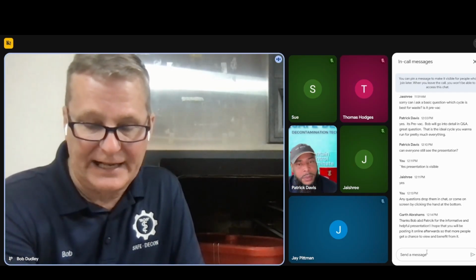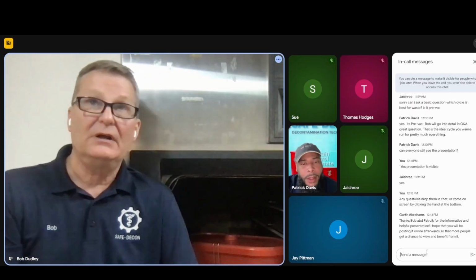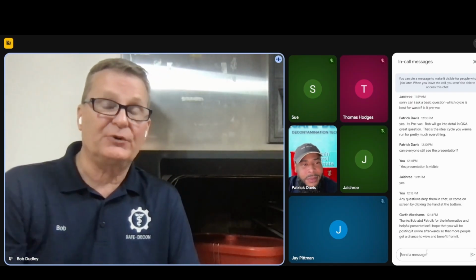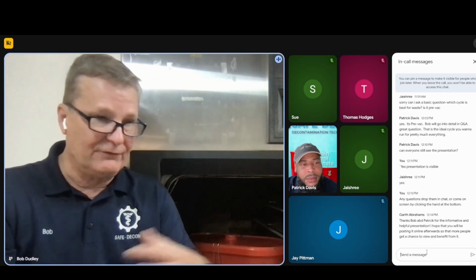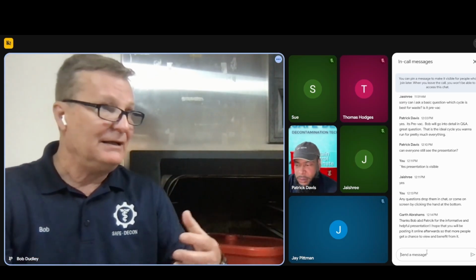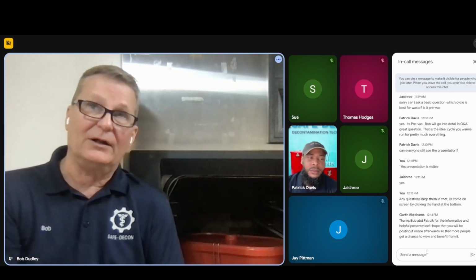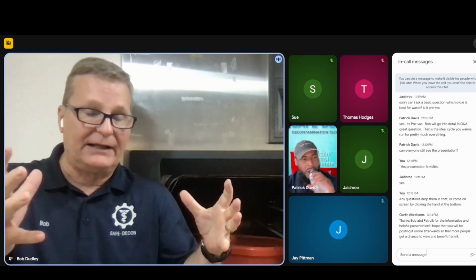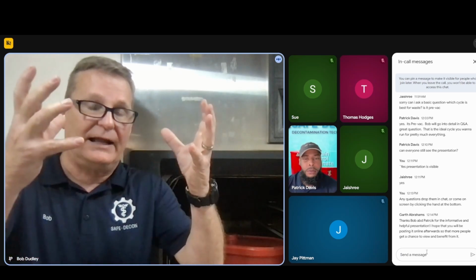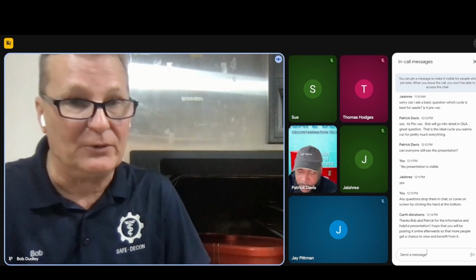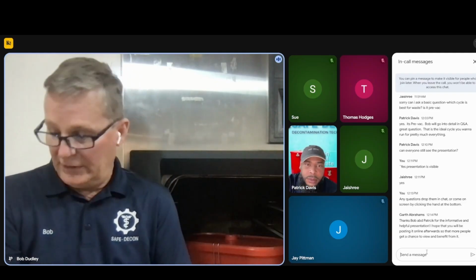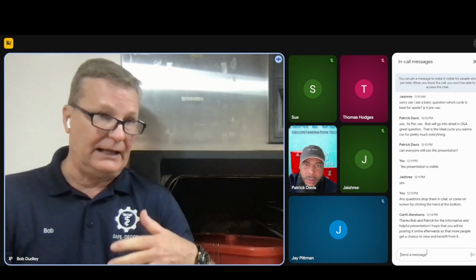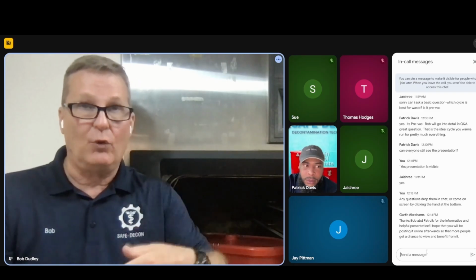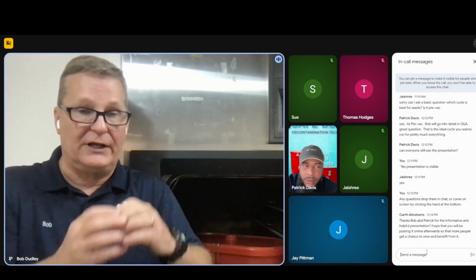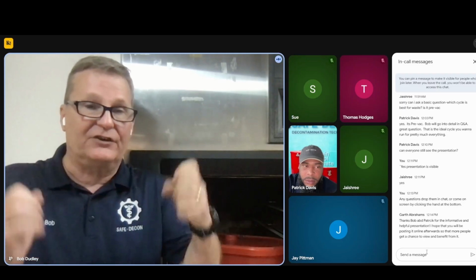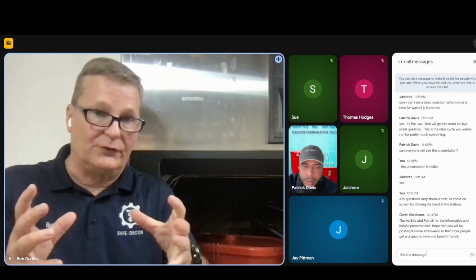Yeah, you definitely want the pre-vac because, one, if there is a bag that is closed, the pre-vac cycle has an opportunity to bust it open. And again, everywhere I go, they're supposed to open the bags, but part of the problem with opening the bags is you create a potential aerosol effect, when the bag opens, it collapses and whatever air comes out can actually get out. So a lot of people really don't want to fool with that. One of the reasons why I like the pre-vac, and I always, when I'm the technician, put the four preconditions, is to give it more of an opportunity to expand that bag and contract it to get it to blow open and expose the contents to that steam and heat.